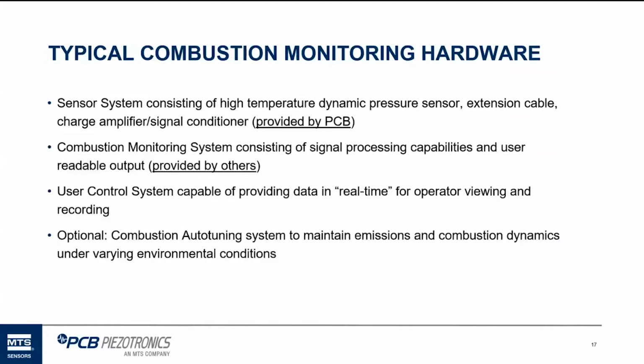Typical combustion monitoring hardware is a sensor system, which we supply, and that's going to be a dynamic pressure sensor and extension cable. So the sensor itself is going to have a hard line, high temperature cable on it, and depending on the length, how far you need to get out of the heat zone, you're going to stop there with that cable and then go on to a soft line extension cable. And then that extension cable is going to run into a charge amplifier and signal conditioner. So those are the parts that we can provide to a system.